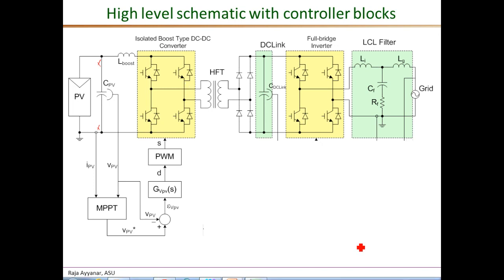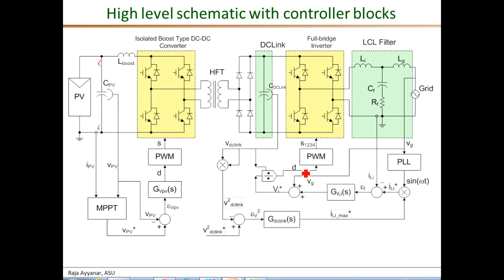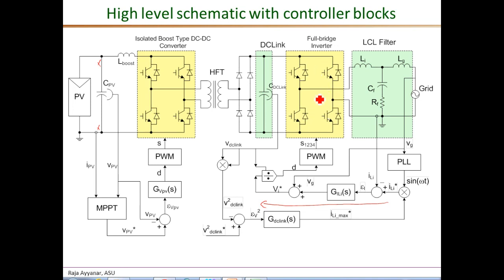The DC-AC stage has two control functions: it needs to control the current injected to the grid, and it needs to regulate the DC link voltage. This is done in a cascaded control fashion, with an inner current control loop and an outer voltage control loop that controls the DC link voltage magnitude. In the inner current control loop, a sinusoidal current reference is compared with the actual grid current, and the error is processed through a current controller — with some feed-forward, which we will discuss in later videos — to directly control the modulation index and phase relationship of the DC-AC stage.